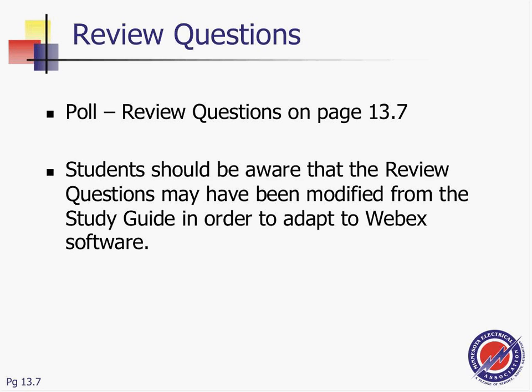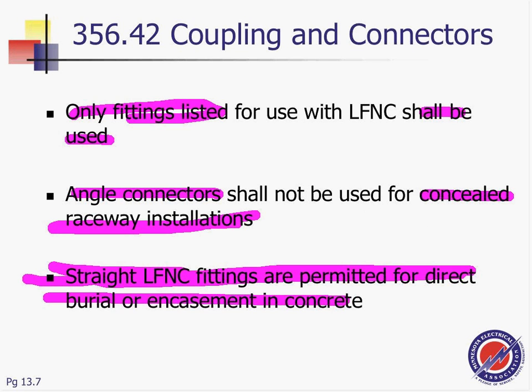So let me ask you guys, how many of you have installed this wiring system? Anybody installed Liquidtight flexible non-metallic conduit? You can get away with a lot of applications, guys. You can get away with Liquidtight flexible metallic conduit in many places, but there are some good places where you can use Liquidtight flexible non-metallic conduit. The only things that come to my mind are corrosion, concrete encased, and direct buried. That's when I'm thinking of flexible LFNC, especially type B.